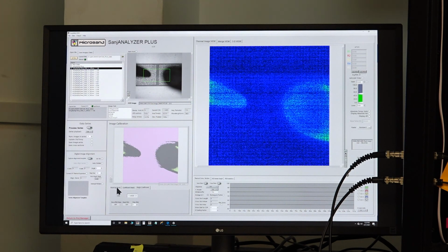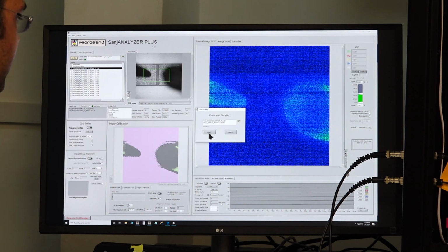Although this is fine for getting a temperature average over a region, sometimes there may be some non-uniformities in our devices in the active region. So that non-uniformity in the growth of the active region would be reflected in the non-uniformities in the coefficient map. So to get a proper point-by-point temperature map, we need to have a point-by-point thermoreflectance map. That we load here. So we had already corrected the calibration file, which is stored here as 10S1. We click this and we click on load.